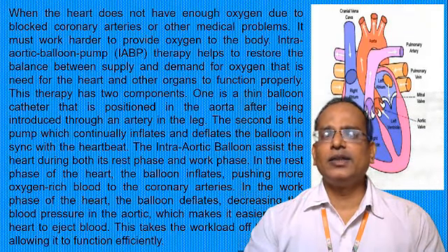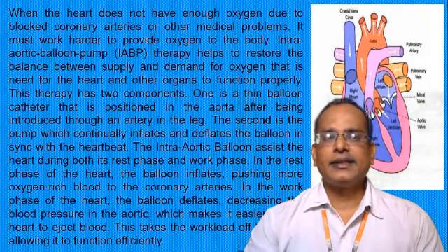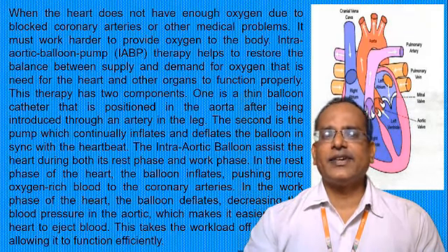One is a thin balloon catheter that is positioned in the aorta after being introduced through an artery in the leg. The second is the pump, which continuously inflates and deflates the balloon in the aorta, synchronized with the heartbeat.